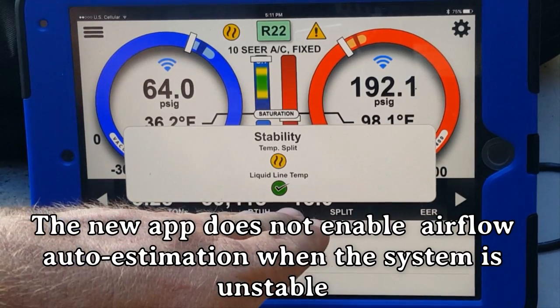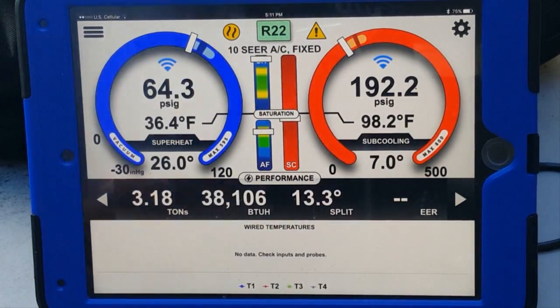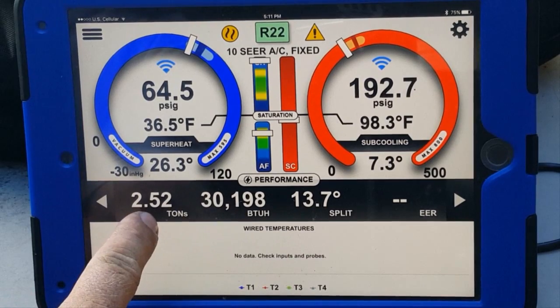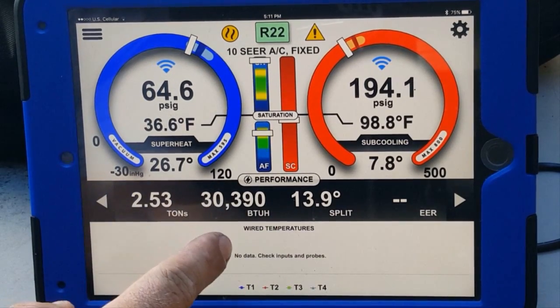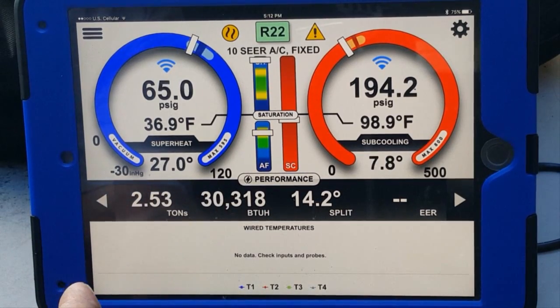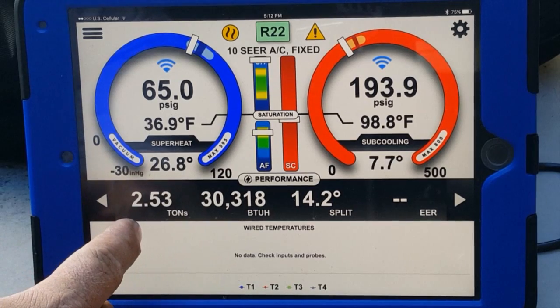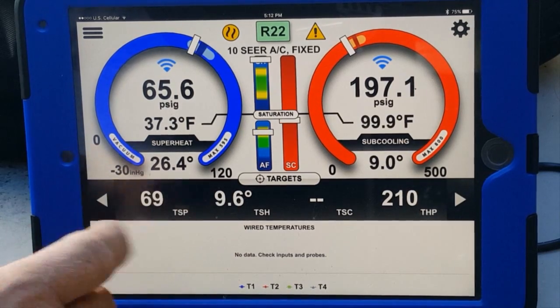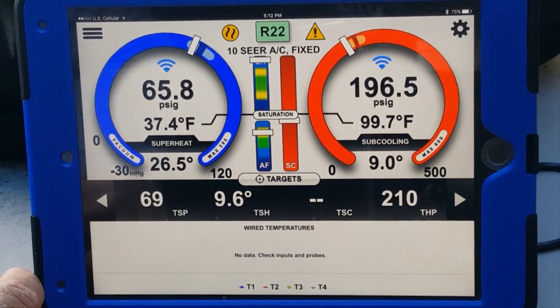The split is showing, then disappearing as it goes unstable again. As you can see on screen, it just adjusted — it's now using 400 CFM per ton, which dropped our BTUs down quite a bit from the earlier overestimate. It compensated and came back to a 400 CFM per ton estimate, putting us at 2.5 tons, 30,000 BTUs — which is perfect for a system that hasn't reached full capacity yet. We'll give it time; if superheat doesn't come down to the target of 9.6 it will warn us.